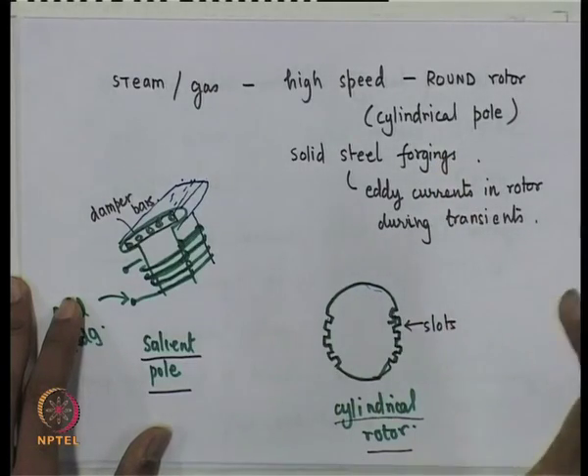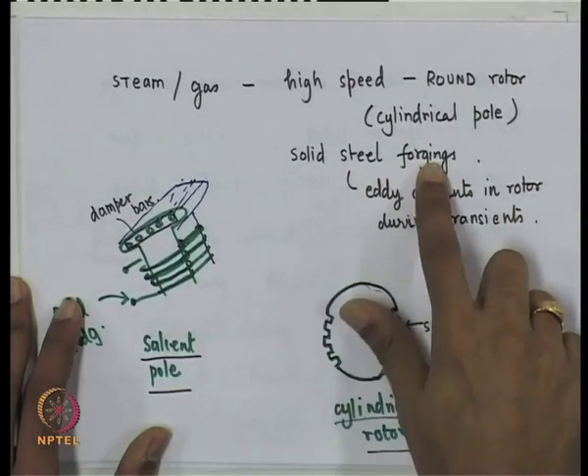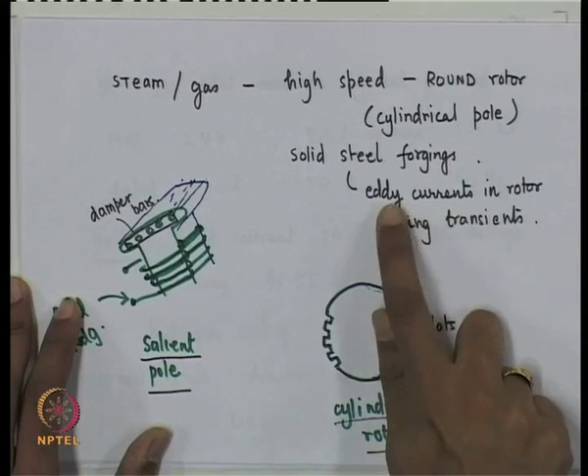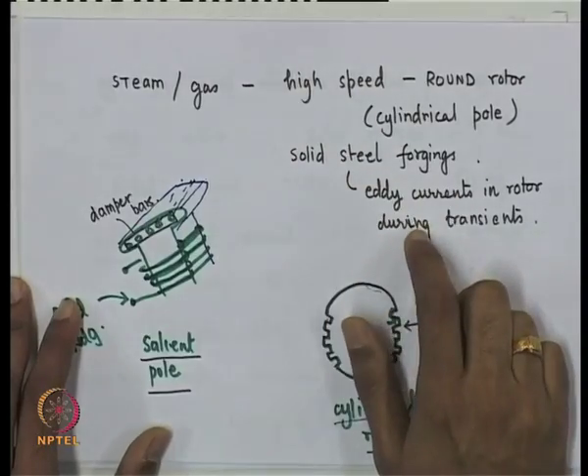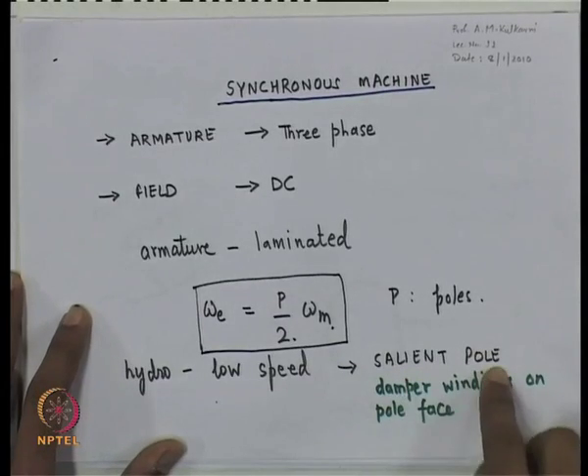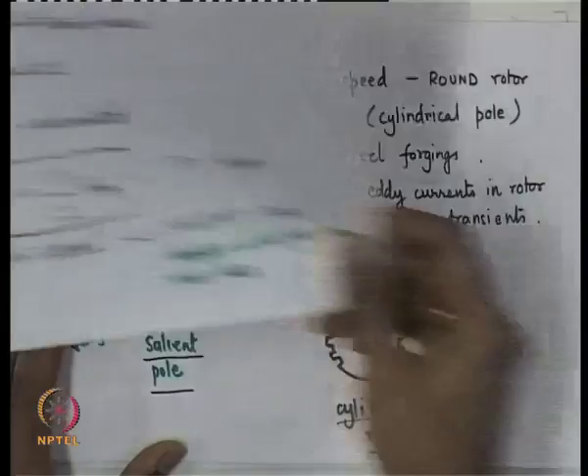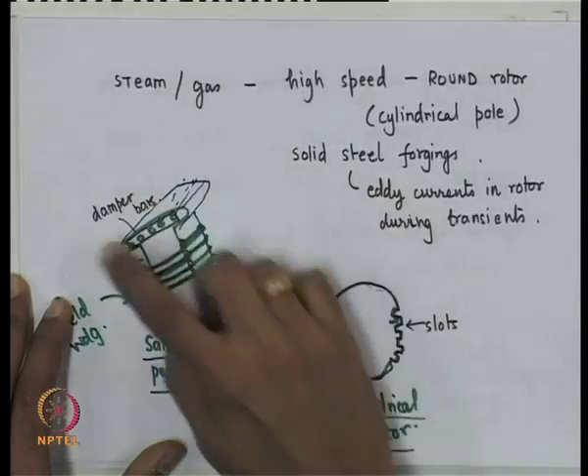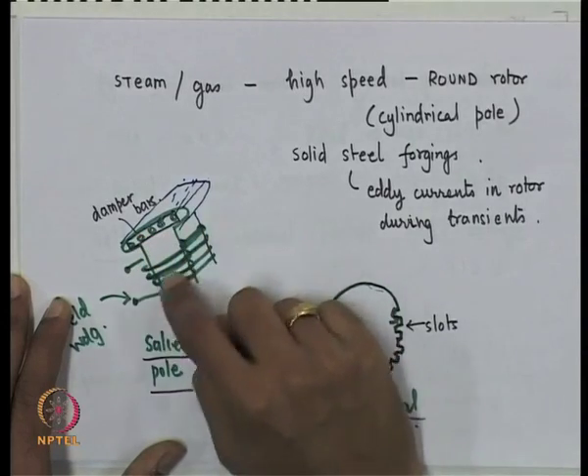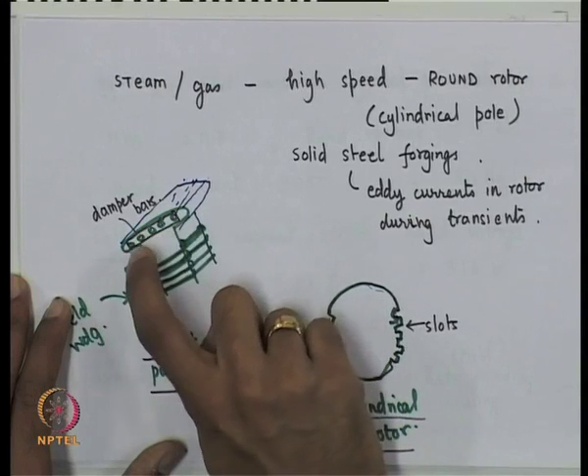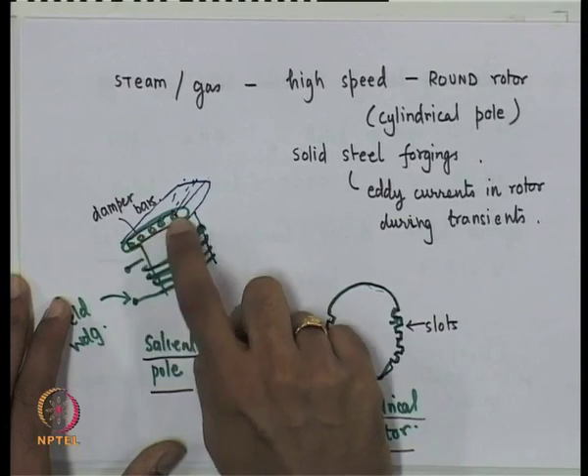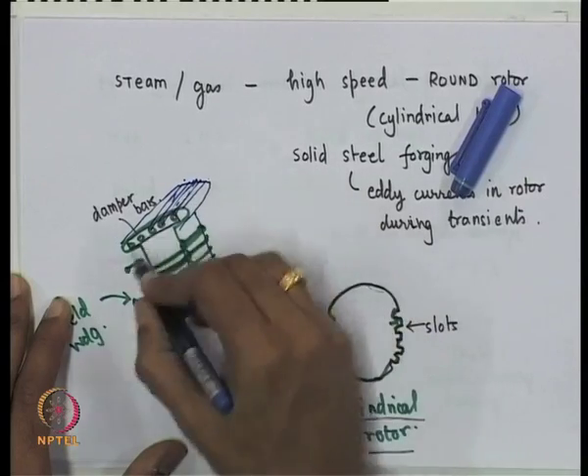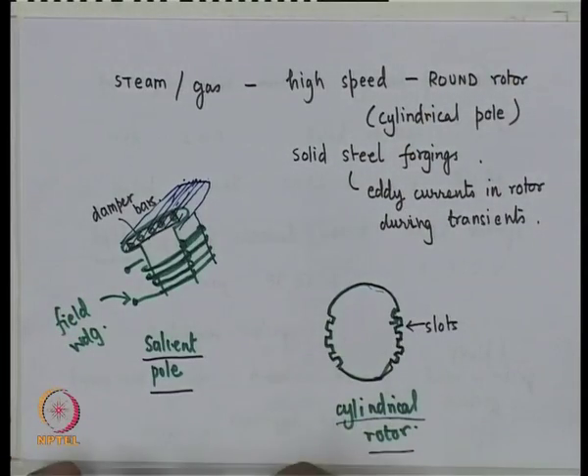In a low speed salient pole turbine machine, the pole faces are laminated. On a hydraulic turbine pole face, the field winding is housed on the pole and damper bars are embedded on the pole face, short-circuited at the ends — basically like a cage on an induction machine.